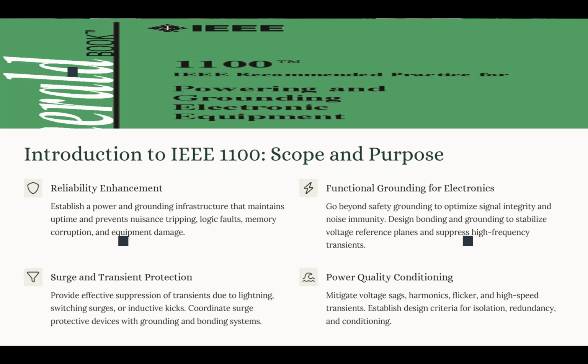We said we want signal integrity. So how do we do that? We basically reduce the common mode voltage difference between the systems so we can prevent logic errors. Or we provide noise immunity by suppressing high frequency transients that can basically cause coupling into data lines.